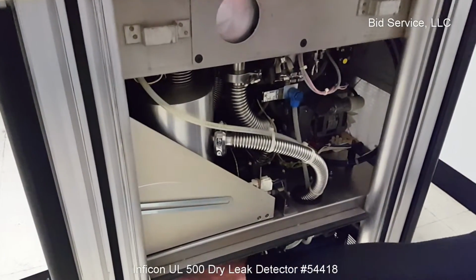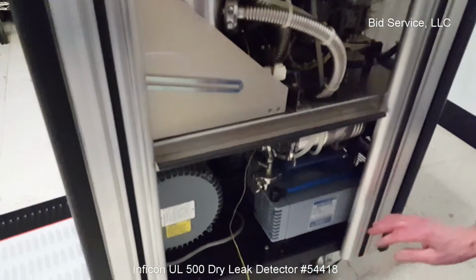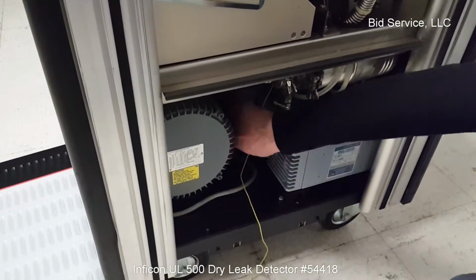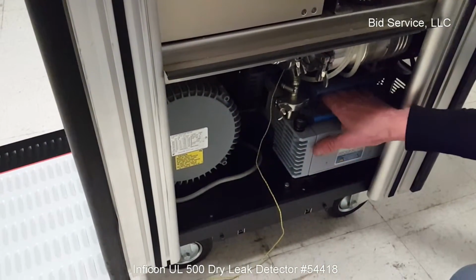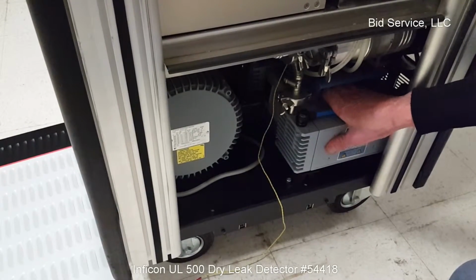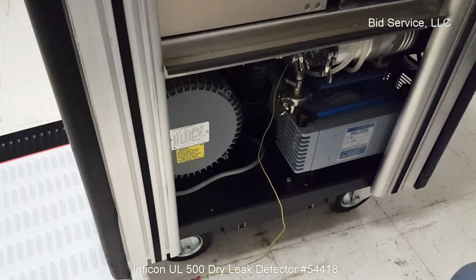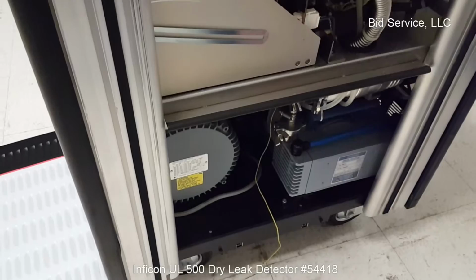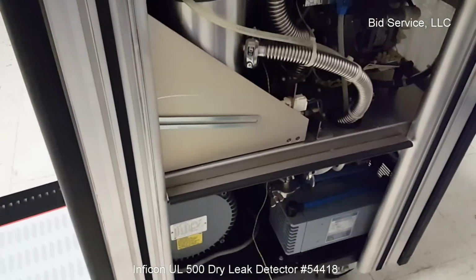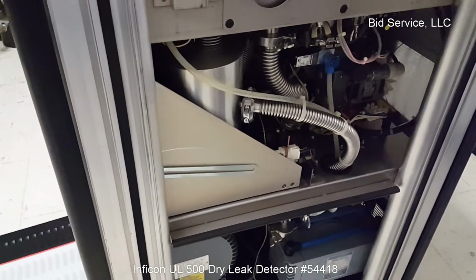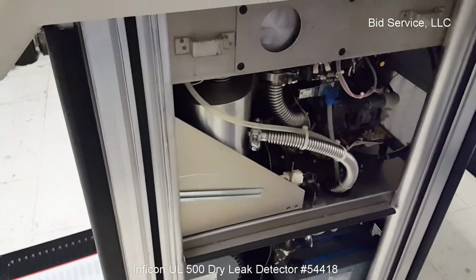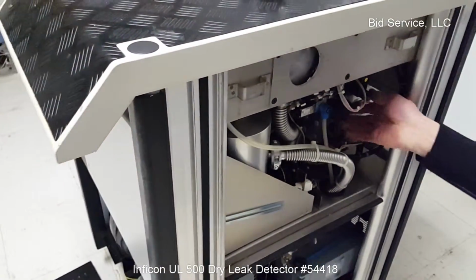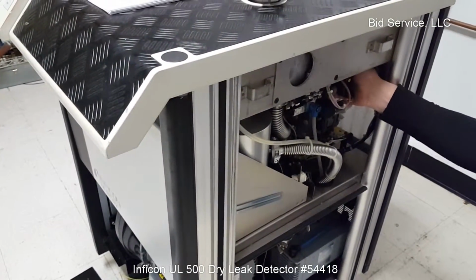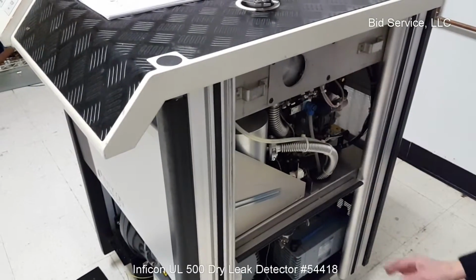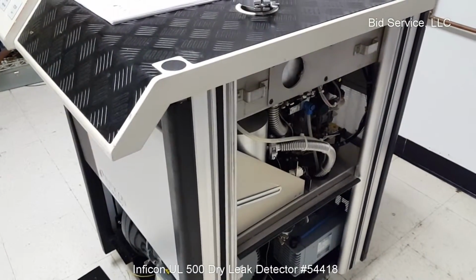The scroll is the backing pump, which supports a double-headed turbomolecular pump here. It is a very, very clean vacuum system. Also, when we turn the system on, we will also show how it does its own internal calibration. And mounted inside is a calibrated leak source that the machine can reference.